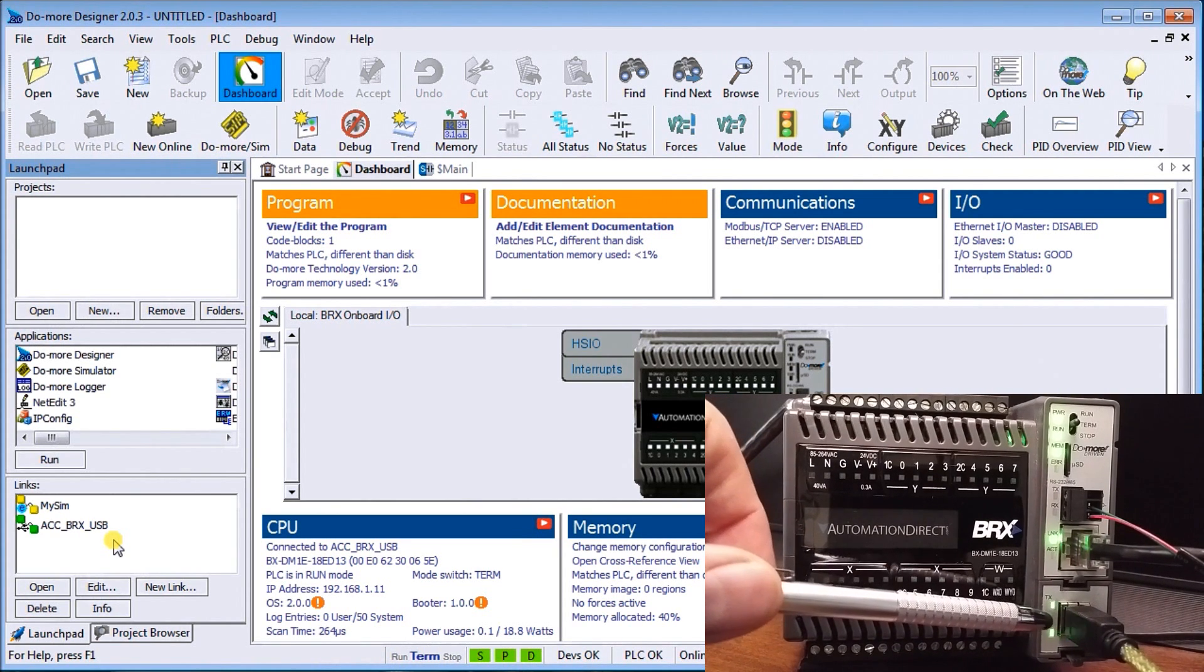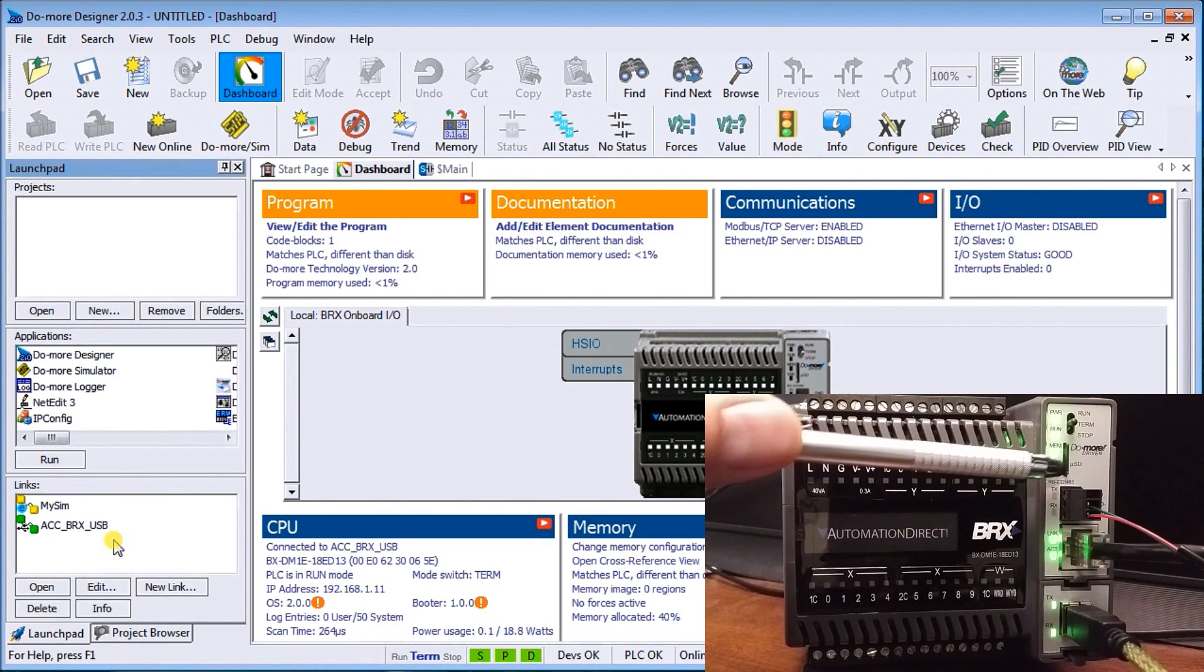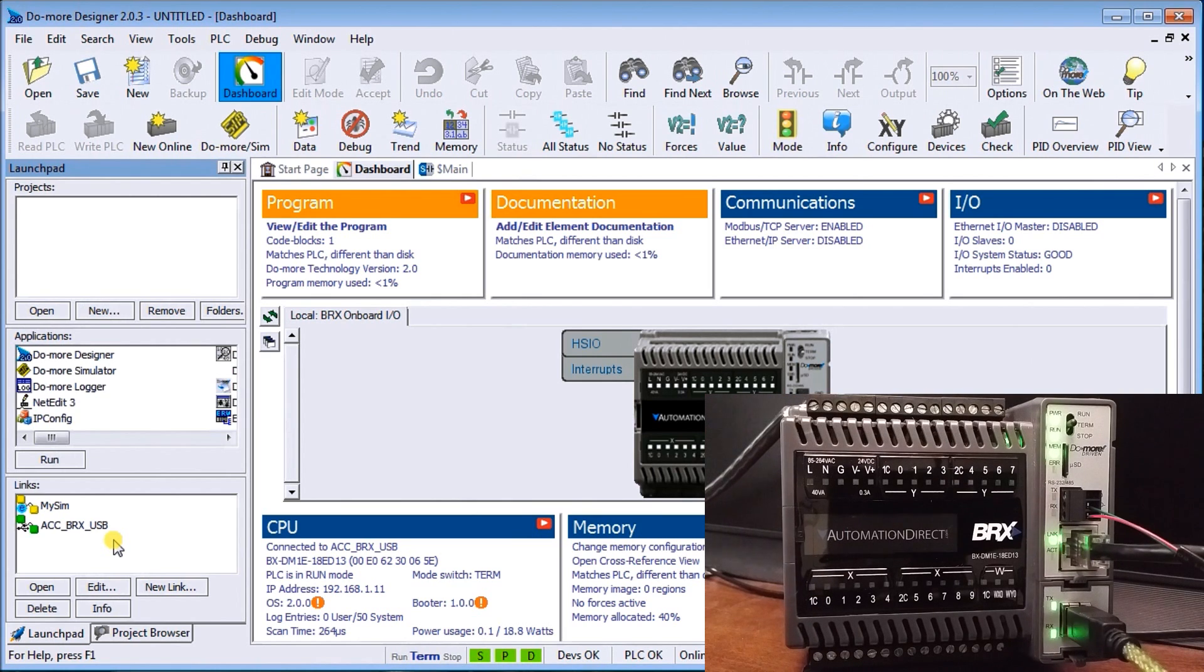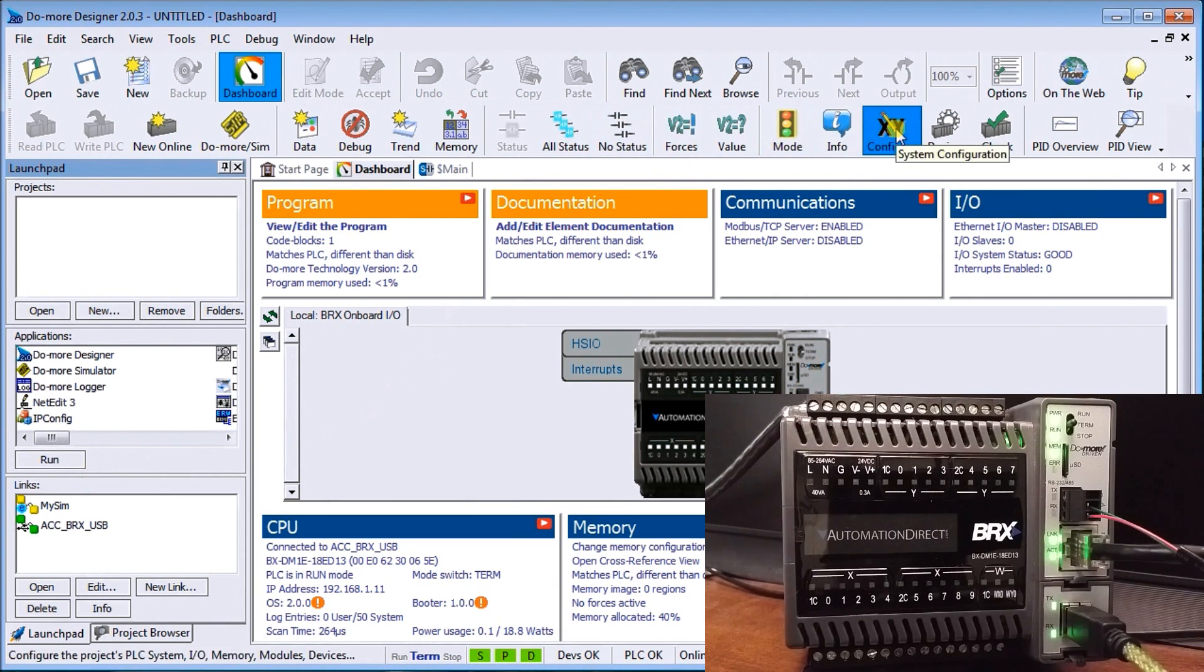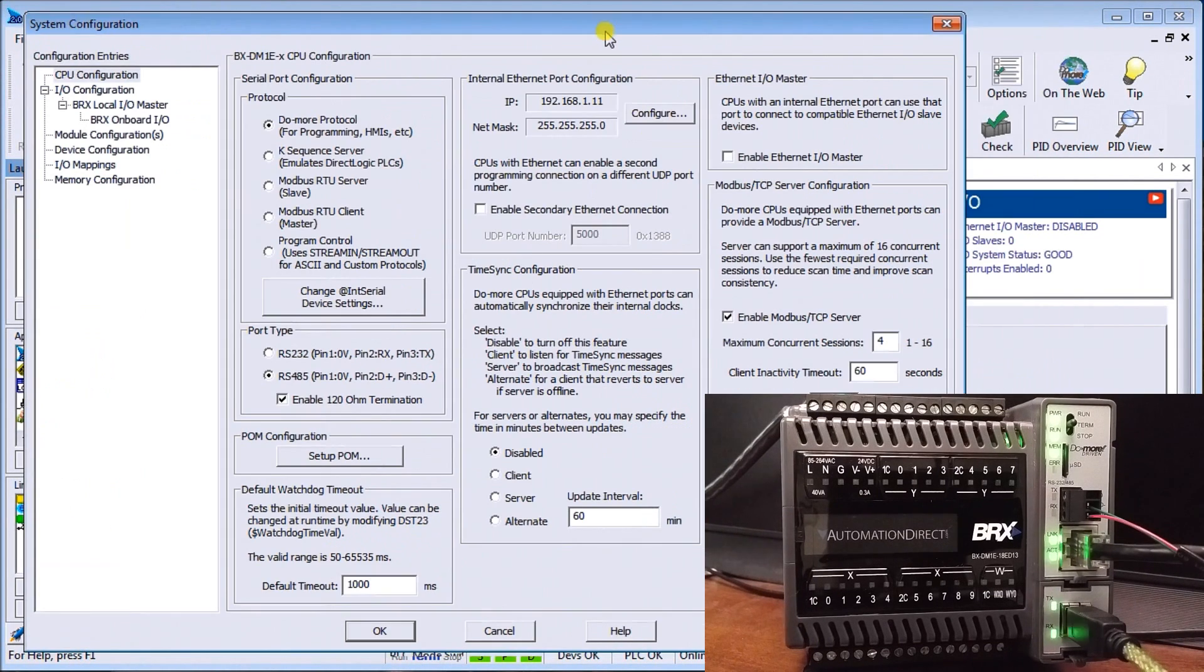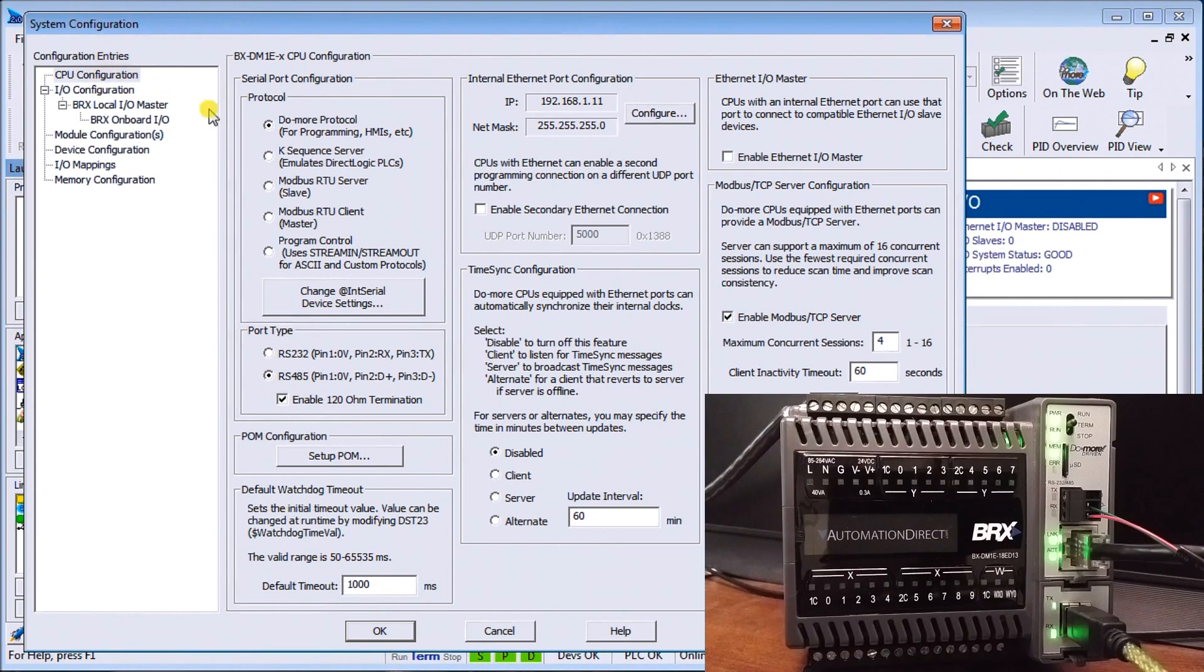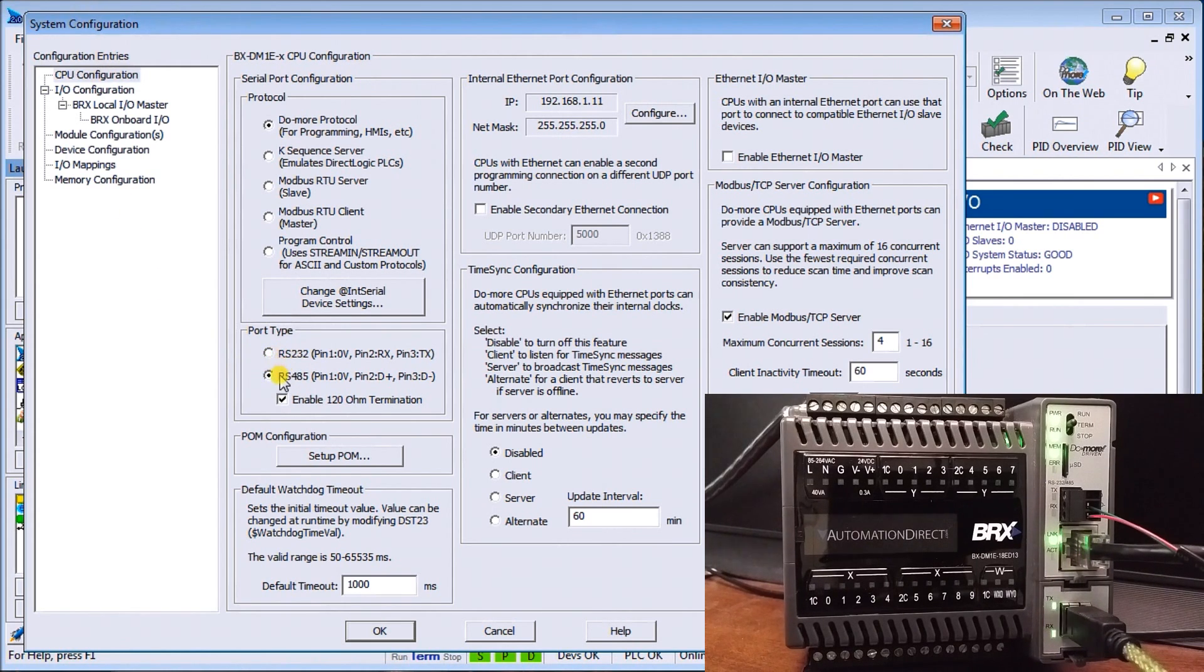You can see that we have lights on our BRX module that indicate we are communicating. We want to set this up because the default currently is RS-232. In order to do that, we go to our online menu bar here and go to configuration. Under system configuration, always go from top to bottom because as you change things at the top, they automatically adjust as you go down. In our case, it's going to be RS-485 and we're going to enable that 120 ohm termination resistor.